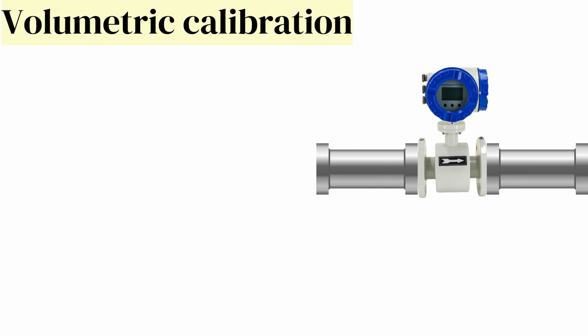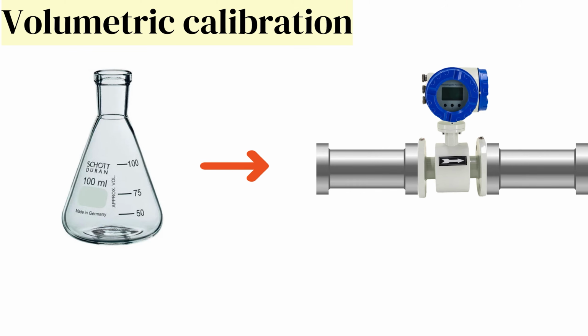3. Volumetric calibration. Similar to gravimetric calibration, but instead of weighing, the fluid is collected in a calibrated tank or vessel for a specific period. The volume is then used to determine the flow rate.